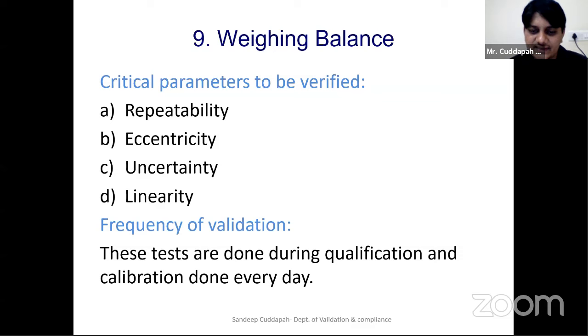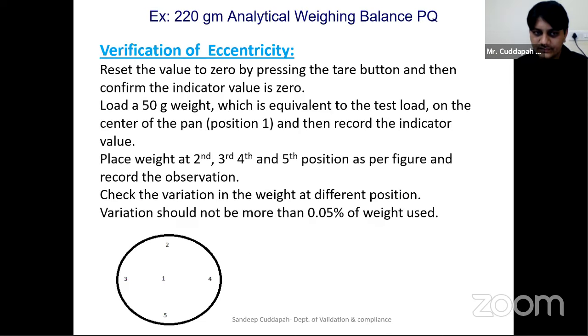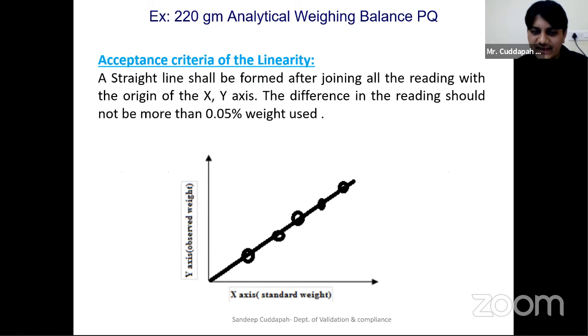How you do the linearity test is, suppose you start by keeping a smaller weight on the weighing balance, then you place some 100 grams or something, then you place 200 grams, then 300 grams. As you increase the weight, you verify whether your weighing balance is also reading the weight exactly or not. You will plot a graph of weight against actual weighing balance reading. If it gives a linear curve, you can say the weighing balance is working and is in a consistent validation program. This is the linearity curve I have told you about.